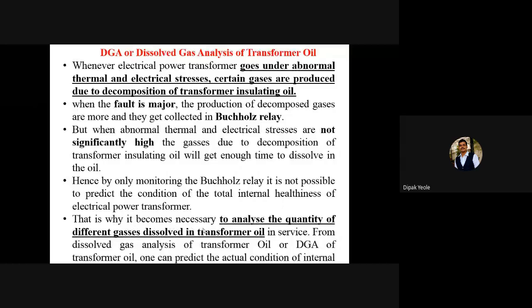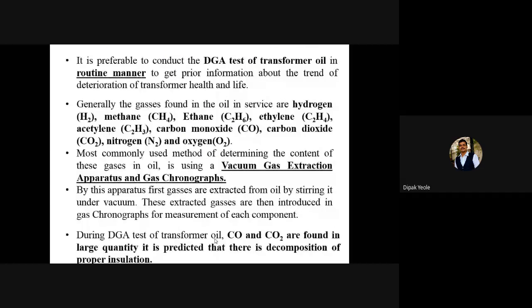That is why it becomes necessary to analyze the quantity of different gases dissolved in transformer oil. The gases available are hydrogen, methane, ethane, ethylene, acetylene, carbon monoxide, carbon dioxide, nitrogen, and oxygen.